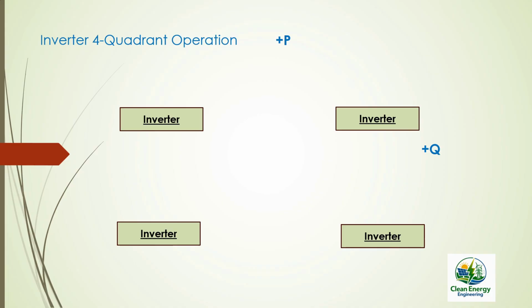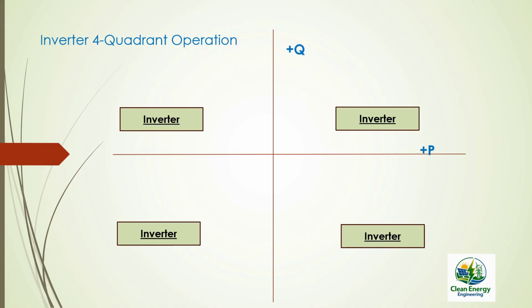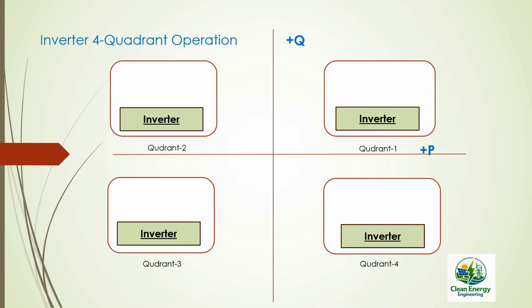curve. Now P is on the X axis, Q is on the Y axis. The 4 quadrants are numbered from 1 to 4 in anti-clockwise direction. Modern inverters operate in all 4 quadrants, meaning they can supply or absorb active power and supply or absorb reactive power. So when grid voltage rises, inverter absorbs reactive power. When grid voltage drops, inverter supplies reactive power.